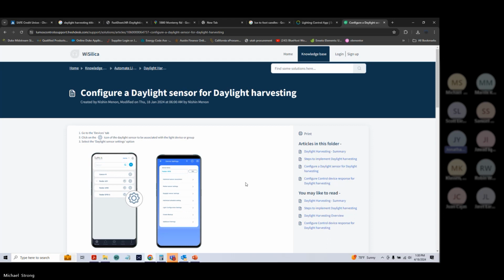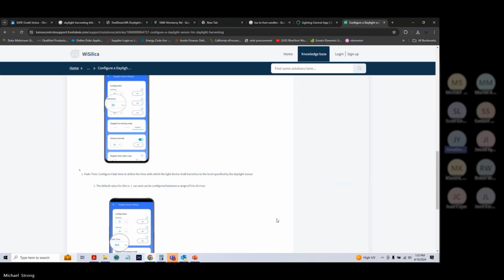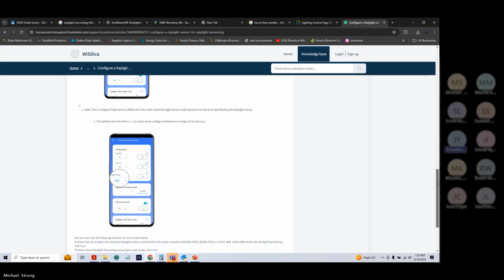For our motion sensors and daylight sensors, we have something called a manual override, so that if someone does want to increase the light level, they'll be able to do so, and the sensors won't immediately turn it to a different setting. The default is 10 seconds for motion sensors or 30 minutes for daylight sensing, but you can increase that value however much you want. That's how our daylight sensing works for all of our products. Again, you have the option to turn motion sensing or daylight sensing on and off depending on what you need, even though it is the same device.